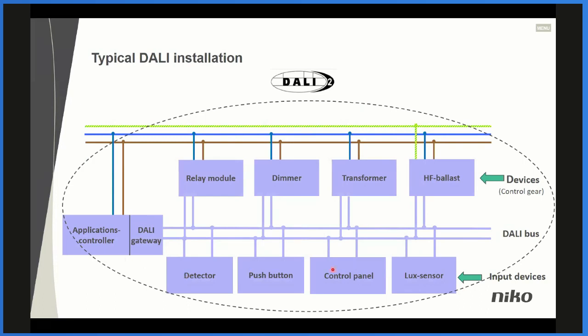That means that we now have input devices, and we still have the control gear up here connected to the mains. Instead of the input devices directly controlling the control gear, as we had in DALI 1, we now have an application controller. And along with the application controller, we have a DALI gateway. And this gateway is actually supplying the DALI bus. You can have all the input devices set up with the application controller that we have here. So that means we now have a DALI system where you can commission both the control gear and the input devices in the same system. That's a great advantage when you are operating in commercial buildings. That means you can actually have both in the same way.